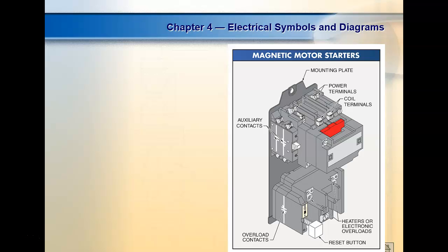So what are our 3 types of relays? We have a control relay. All the contacts of the control relay will be in the control circuit. And we have a contactor. Contactors might not have any contacts in the control circuit, or they can, but they're going to be auxiliary contacts. They're going to be low current contacts, right? But it is a power relay. It's designed to handle power, but it has no overload.